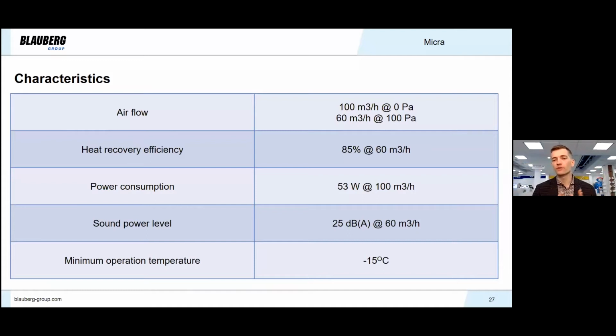The target operation point for this specific Micra is 60 cubic meters per hour at 100 Pascal. Heat recovery efficiency is 85% at this point. Power consumption is 53 watts or lower. Our goal is to achieve 25 dBA at 60 cubic meters per hour. We will finish acoustic testing soon and we will see the real numbers. Minimum operation temperature is -15. There will be no preheater and afterheater in this unit. Supply fan stop is the freezing protection only.